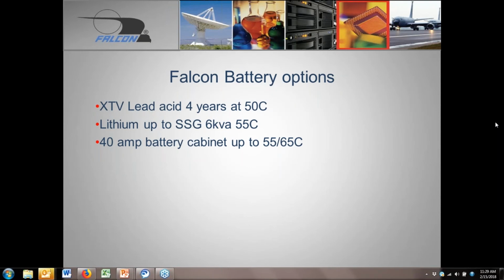How do you know battery condition? How do you get information on it? Battery condition testing remains the same, either through SNMP with a battery capacity test on the interface, or manually through the front panel. It's based on battery voltage within a 10-second test that puts a load on it, reads the battery voltage, and gives you the capacity based on that.